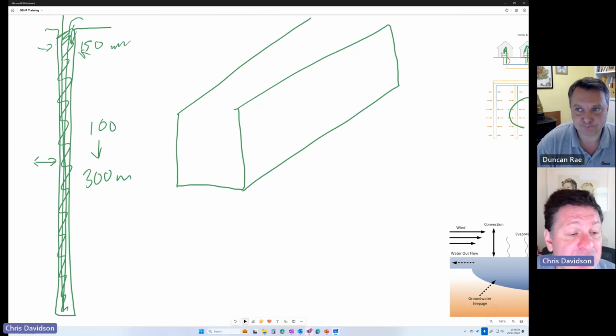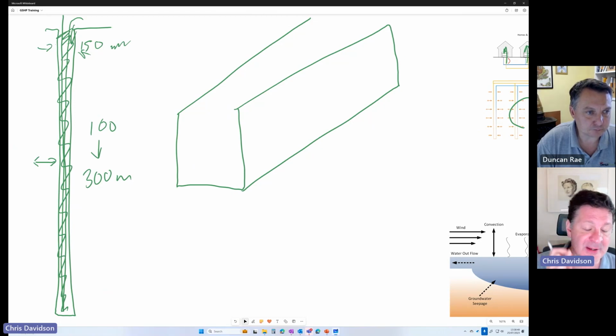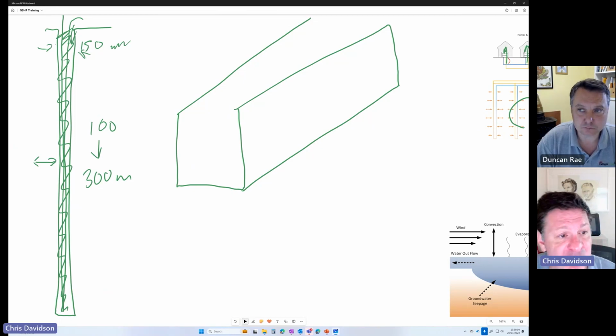It's so variable that any rule of thumb you use is likely to be misleading and frankly useless. The range of output you can get depending on depth of borehole, depending on geology, and depending on nature of your loads, heating and cooling, for example, could be as low as 3 kilowatts a borehole, could be as high as 30 kilowatts a borehole. So applying a rule of thumb to this is very, very difficult, and you're almost certainly going to be wrong. Put it another way, I've given up guessing how many boreholes a ground loop's going to need because I'm always wrong.